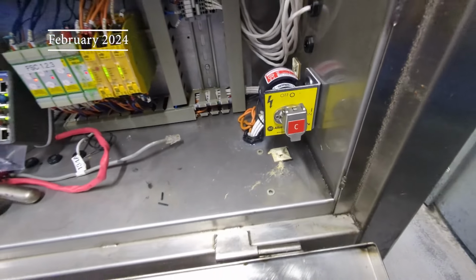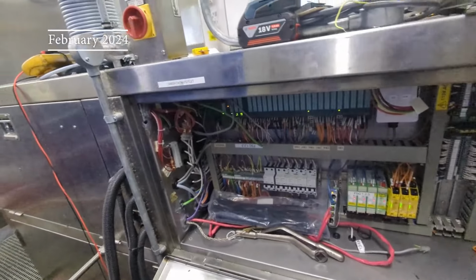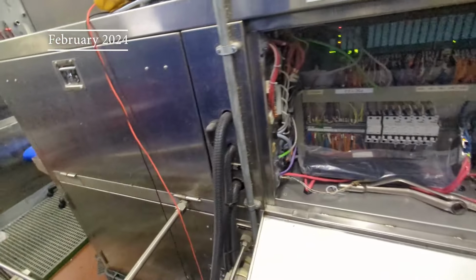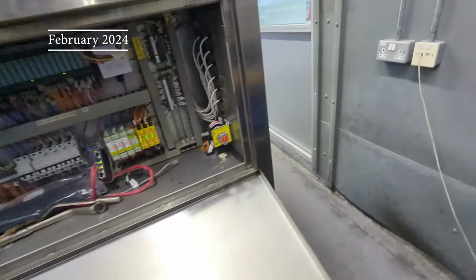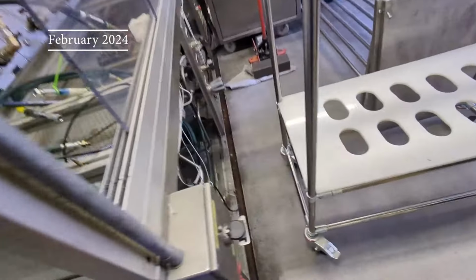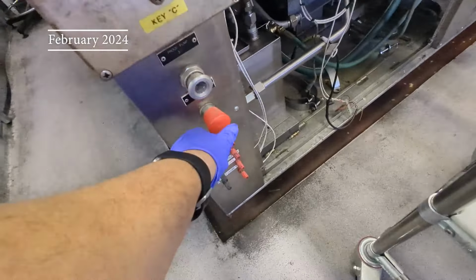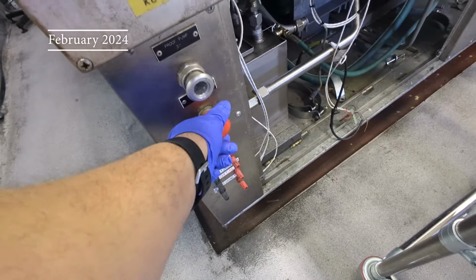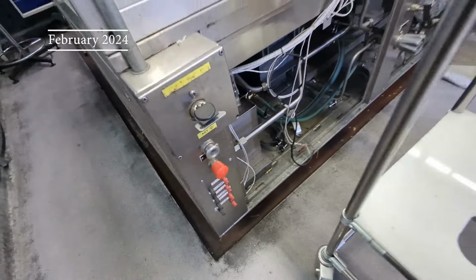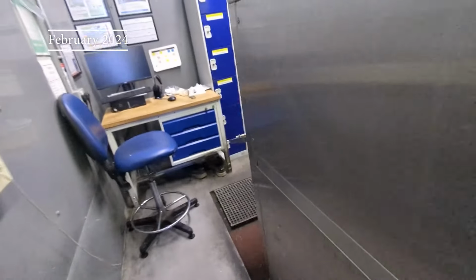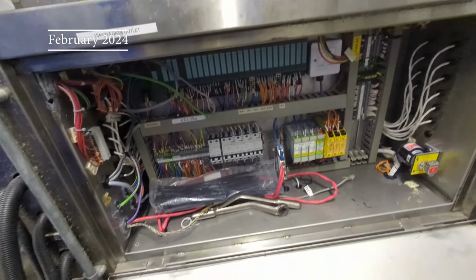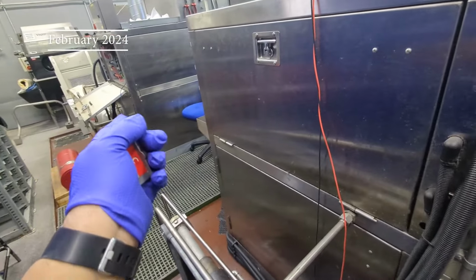Disable it, take the key out, and now what you can do is, so this rig has e-stops on it, and downstairs is a HPU which I can take you to. So this e-stop now will be ignored. You hit that e-stop, nothing happens, and what it means for the electrical guys is that they can come inside this panel, turn off the power and start working in here whilst there's a test going on that rig over there.